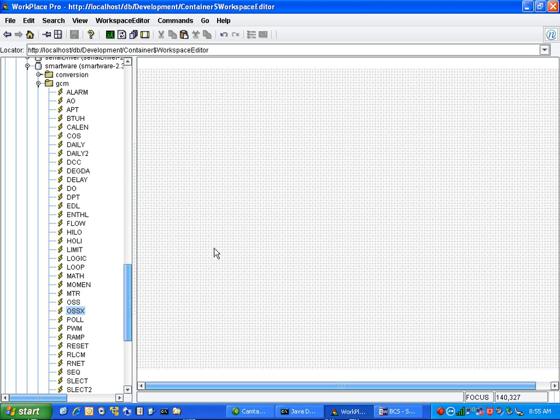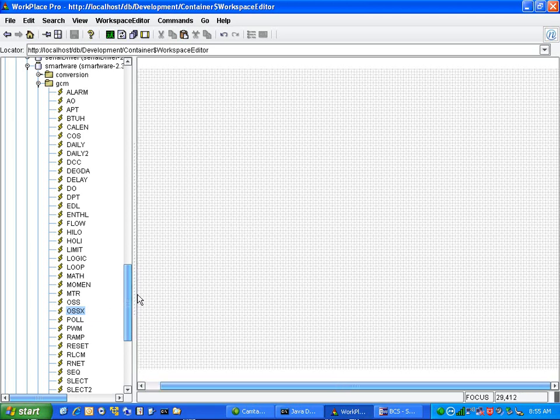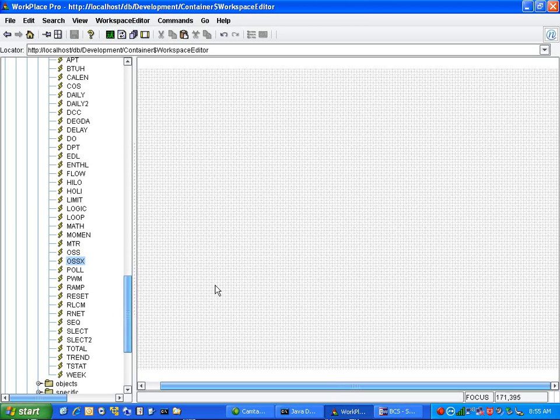Yes, there are also ways to link up to those. You can link to those with special objects, and we had that in our other class, as a matter of fact. It was the way we were able to graphically display and show how we adjust alarm limits with analog command type objects. But no, you're right. If you did have dynamic analog values, you'd probably want to use the select out of the GCM because it gives you the ability to link float status to it.